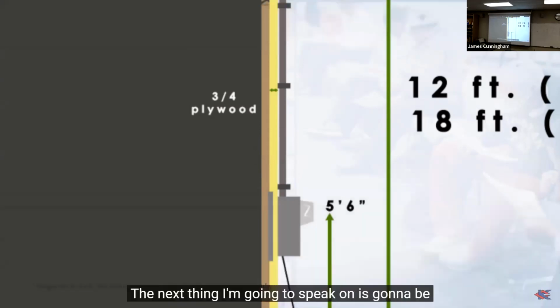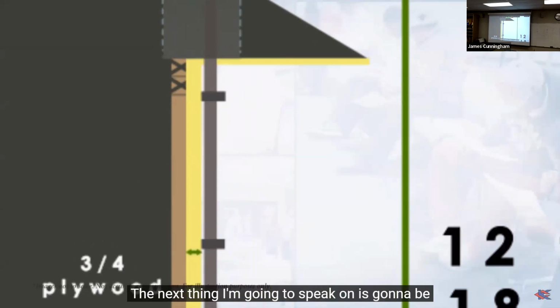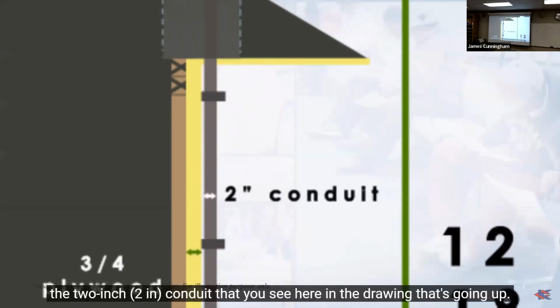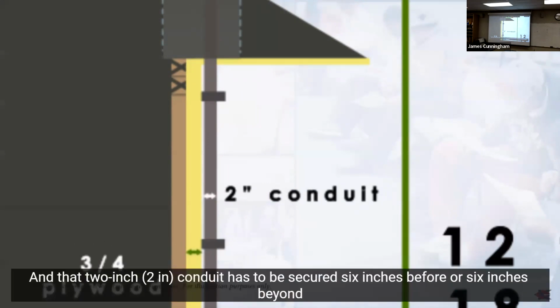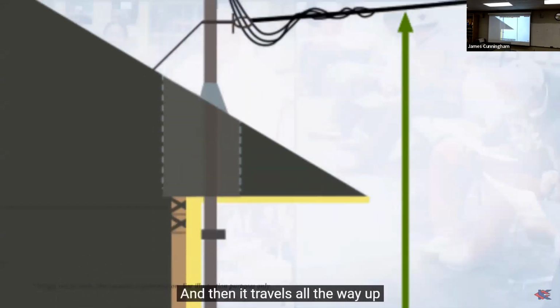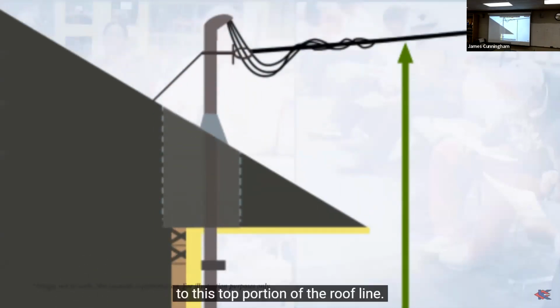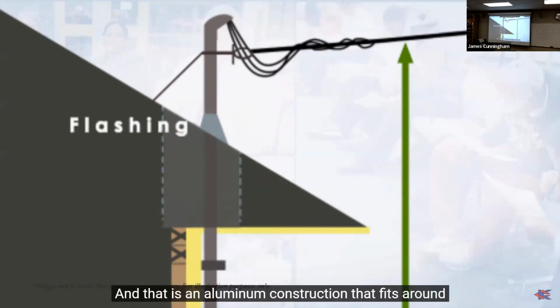The next thing that I'm going to speak on is the 2-inch conduit that you see here on the drawing that's going up. That 2-inch conduit has to be secured 6 inches before or 6 inches beyond the meter can, and then it travels all the way up to this top portion of the roof line. And right here on this roof line, there is flashing. That is an aluminum construction that fits very snugly around the 2-inch conduit to prevent any water from seeping down into the electrical system.